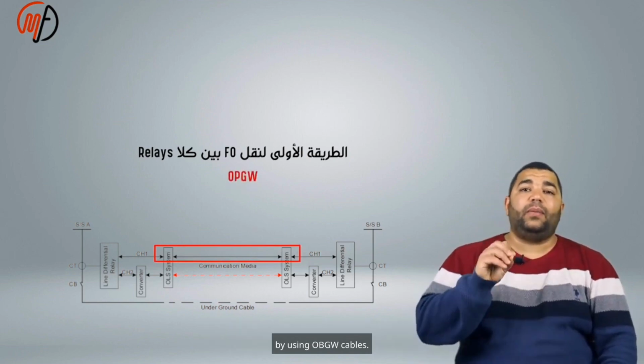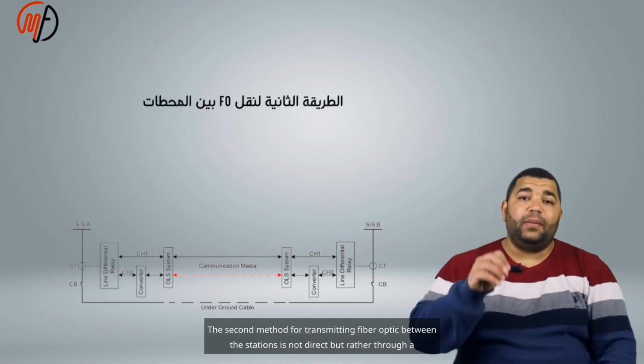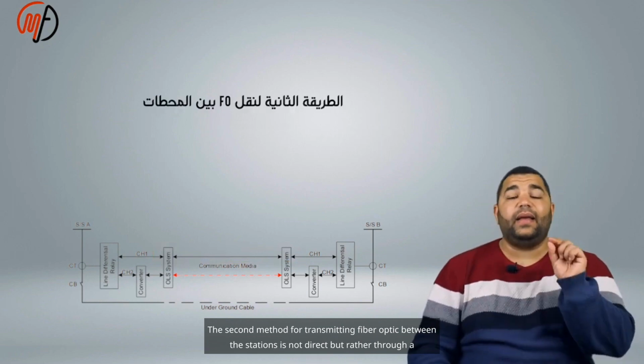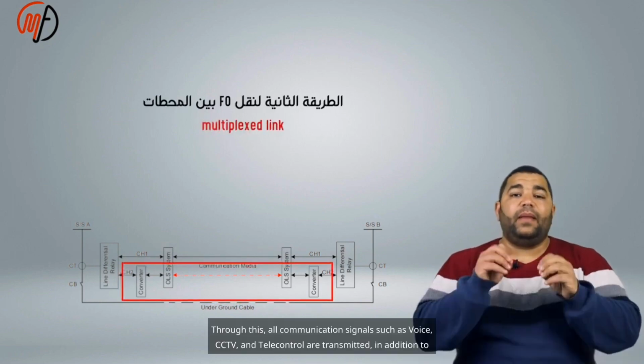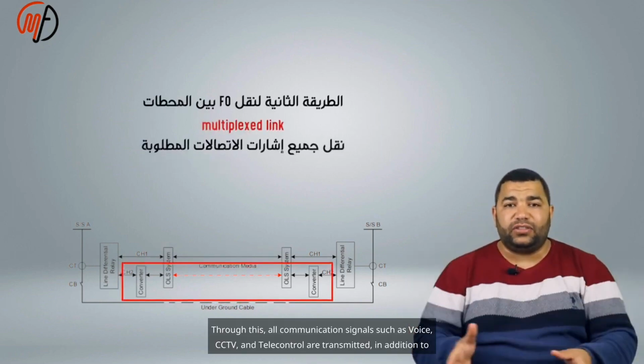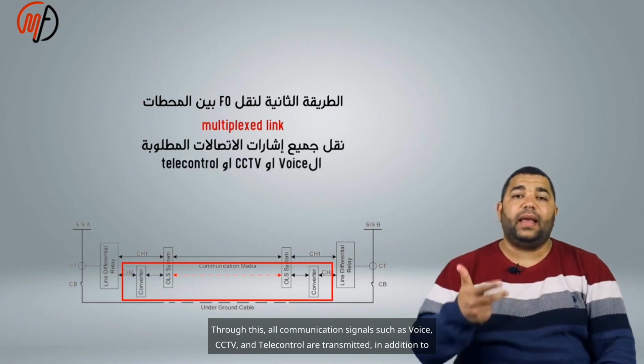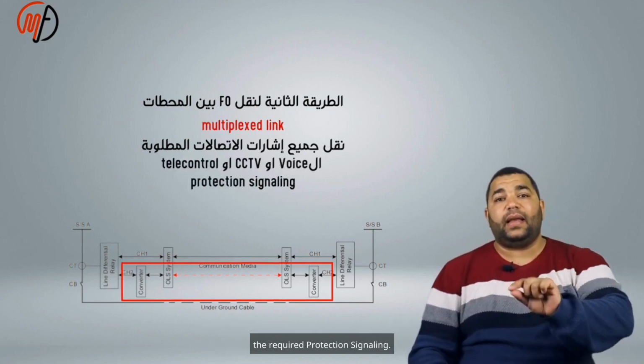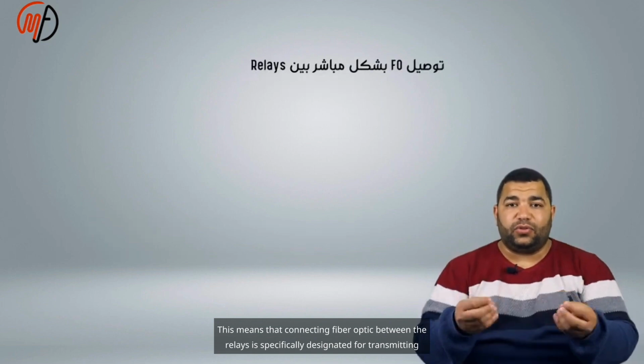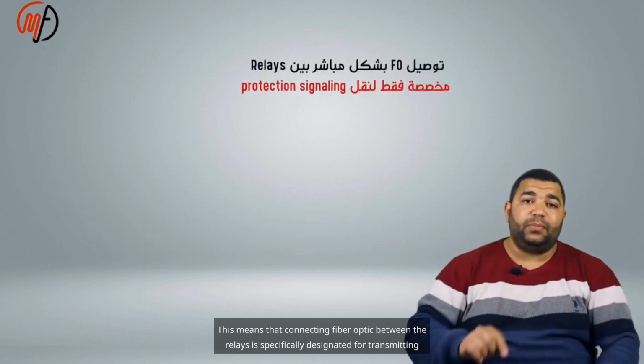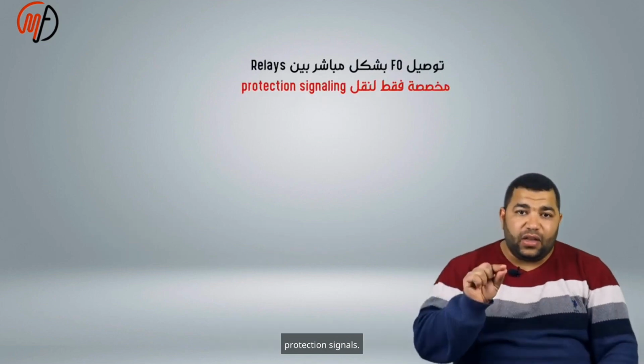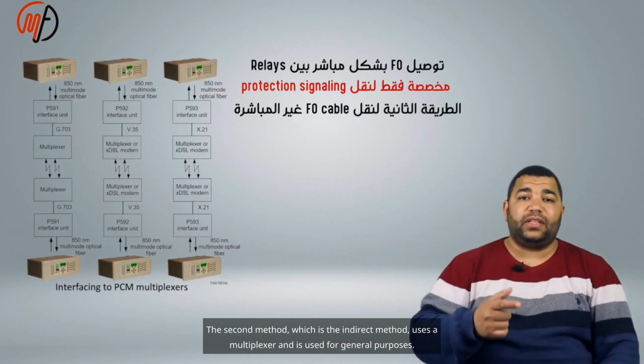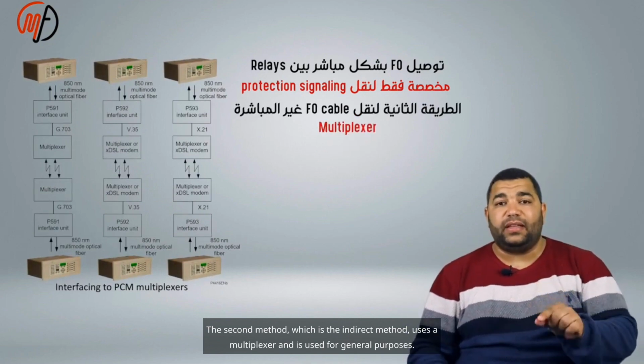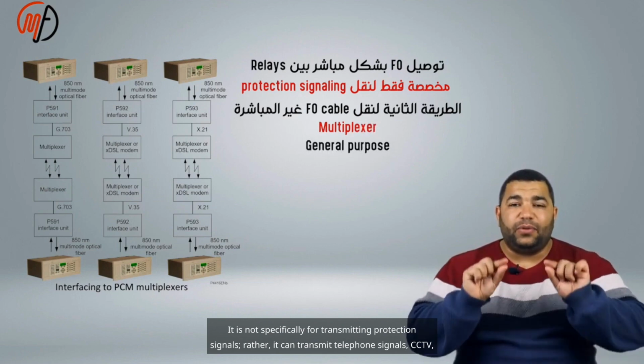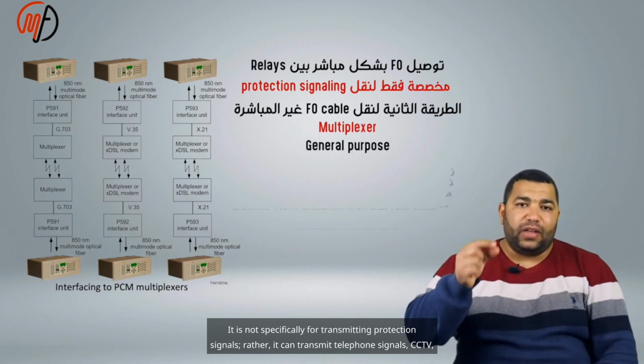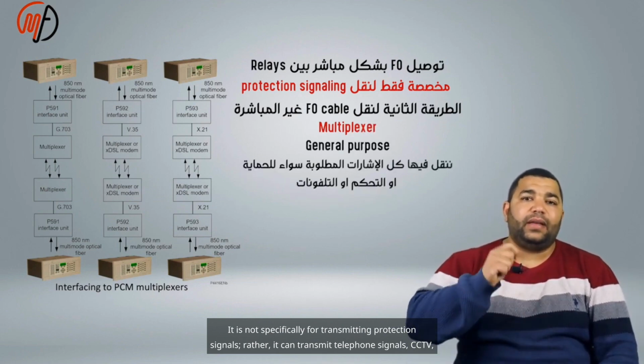using OPGW cables. The second method for transmitting fiber optic between the stations is not direct, but rather through a multiplexed link. Through this, all communication signals such as voice, CCTV, and telecontrol are transmitted, in addition to the required protection signaling. This means that connecting fiber optic between the relays is specifically designated for transmitting protection signals. The second method, which is the indirect method, uses a multiplexer and is used for general purposes. It is not specifically for transmitting protection signals. Rather, it can transmit telephone signals, CCTV, and others.